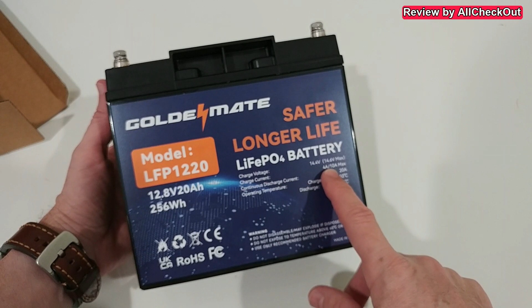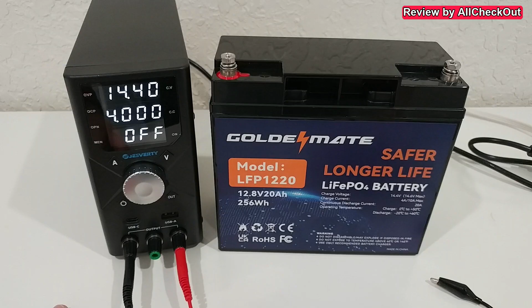Terminal type is T2. Charging voltage is 14.4 volts, charging current 4 amps, maximum 10 amps. Continuous discharge current is 20 amps, at 12.8 volts. If my calculation is correct, that's around 256 watts. They're not saying peak, they're saying continuous discharge current, which sounds like a safe current to me. We could use that for exactly 1 hour, bringing it to 256 watt hours. You also see the charging and discharge temperature range is quite huge, so I'd say you can use it even outside in pretty rough conditions.